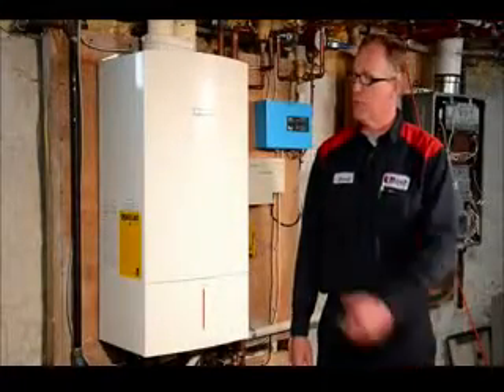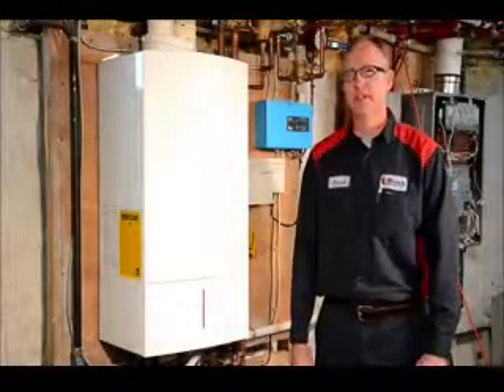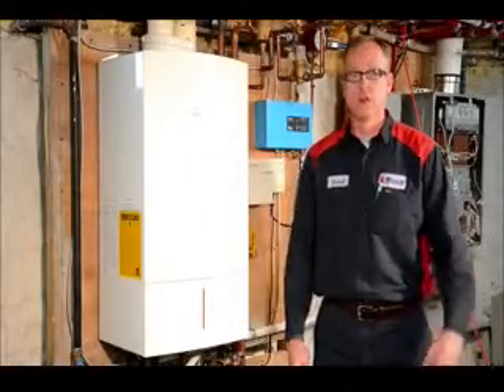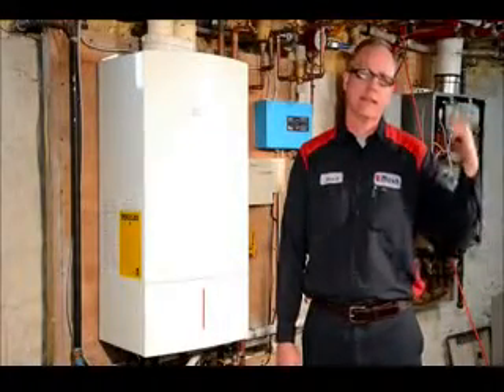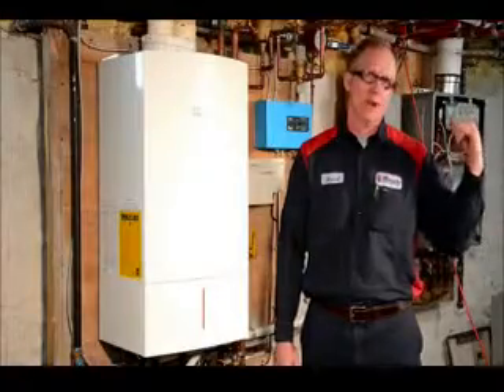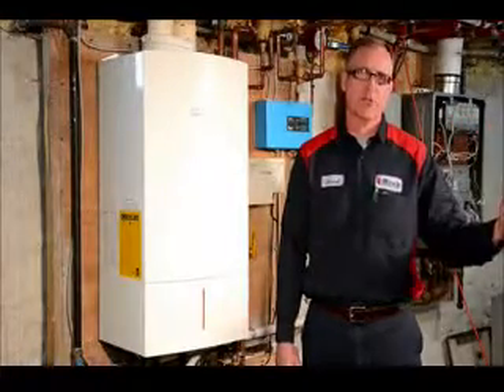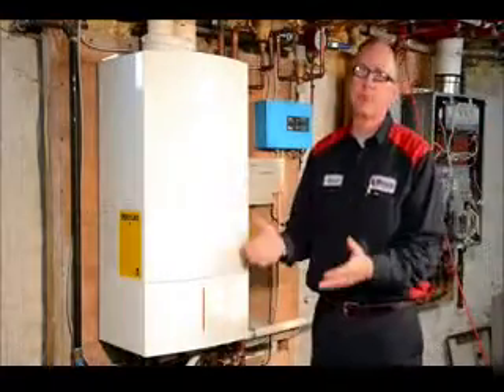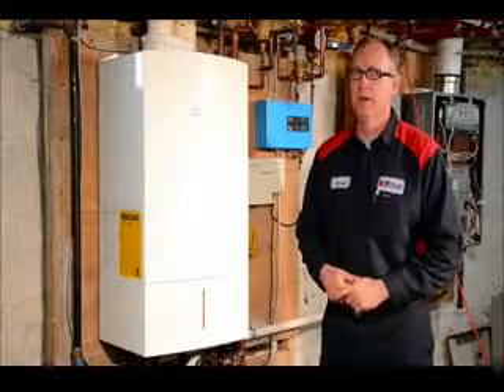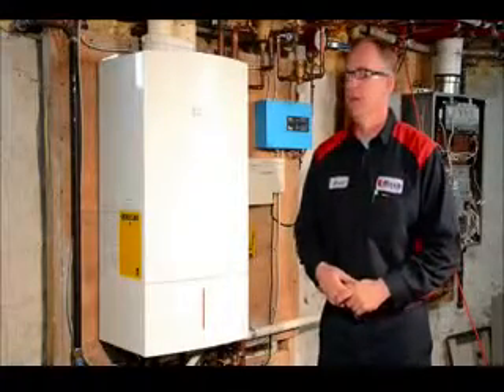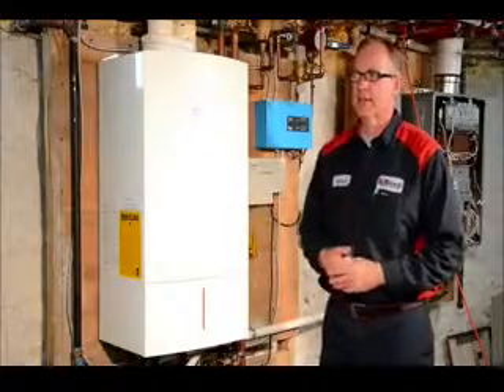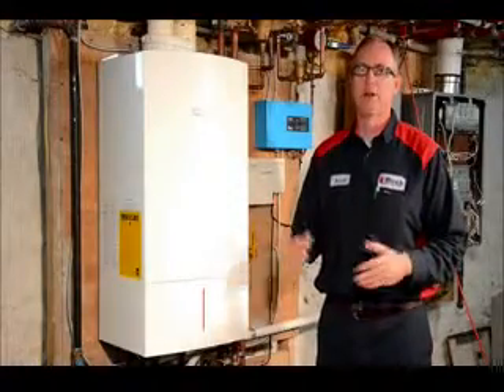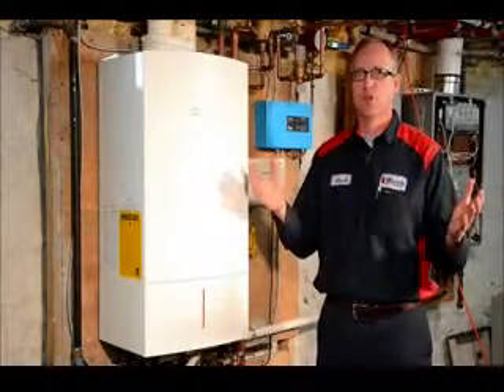We are now here with a Bosch 98% condensing boiler. Earlier we had talked about the Rinnai condensing tankless and the Rinnai hydronic furnace as a means to heat our showroom. Now we're going to discuss our primary means of heating our showroom, and that is through a radiant floor system. This boiler makes extremely efficient hot water that is piped through the floors of our showroom.